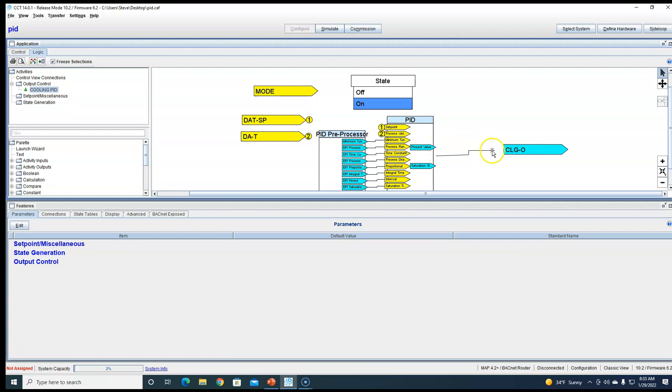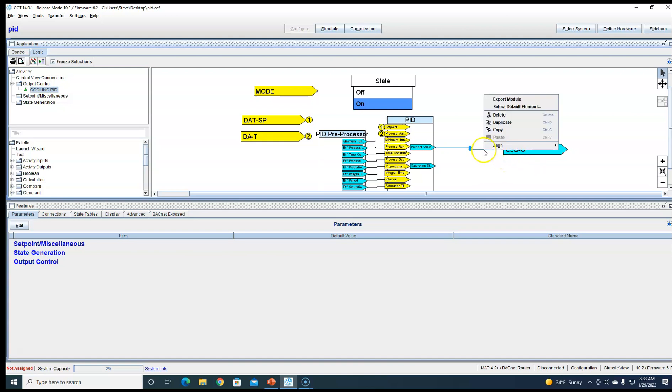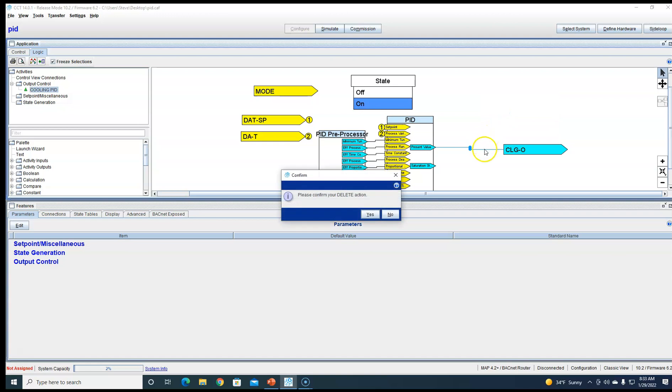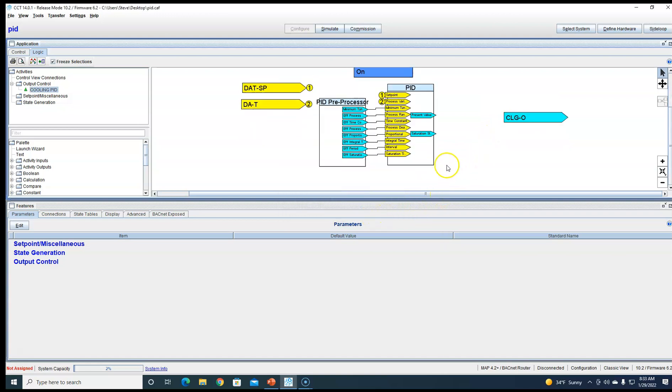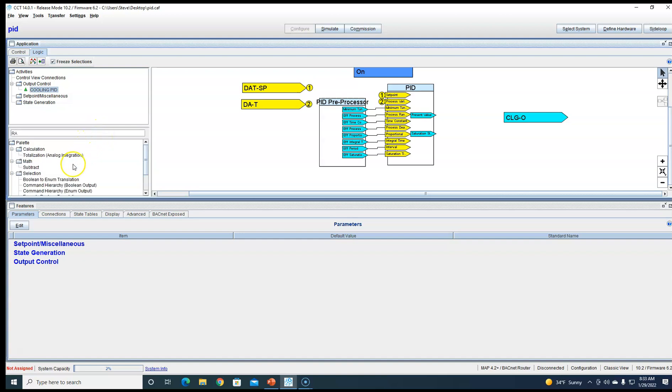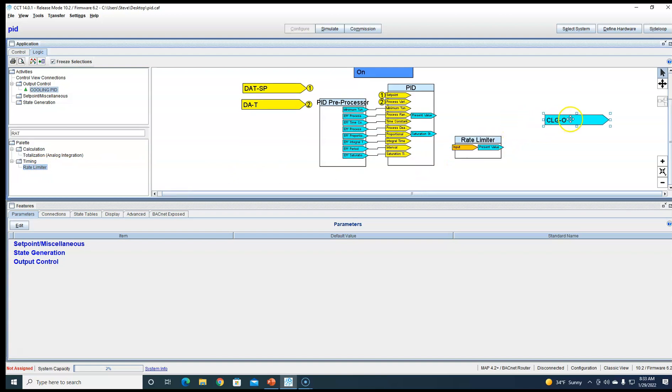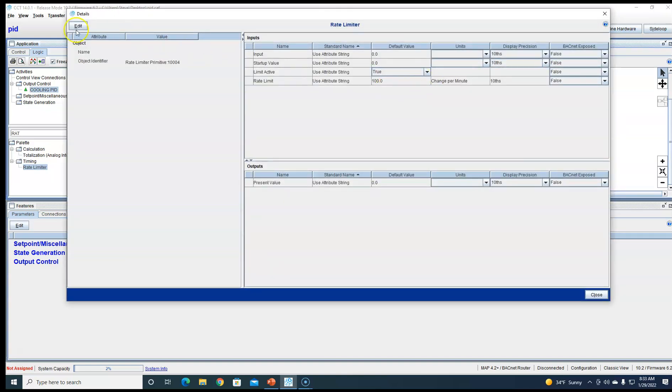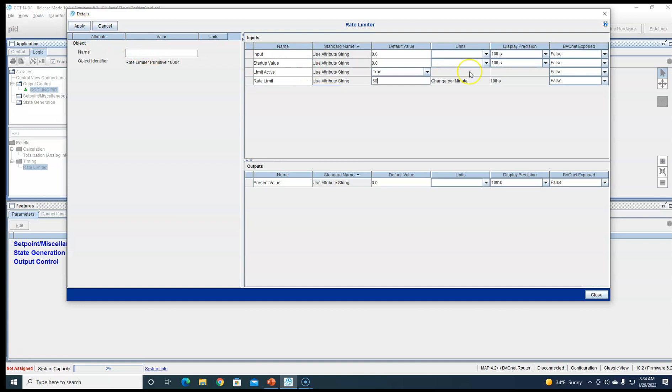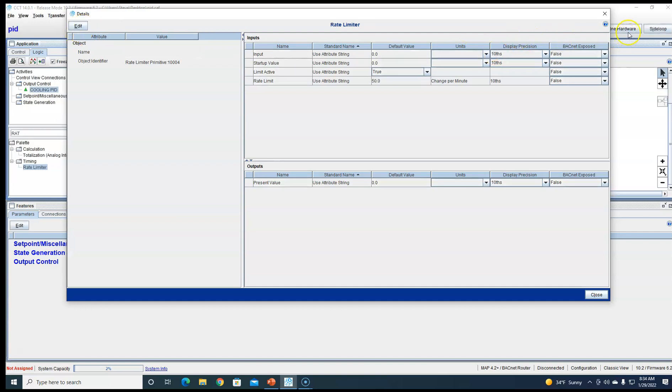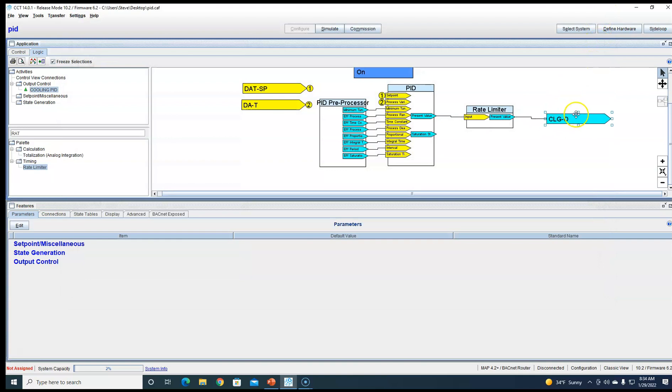Set point to set point, discharge air to discharge air. If you don't like the way that looks, you could always hide these and put numbers in its place. Normally we just connect PID to the output, but today we're going to use a rate limiter. Here to set up the rate limiter, this is changes per minute. So a hundred, that's going to be one minute of change. So if we do 50, that's going to be two minutes of change, so it's going to take two minutes to make a full change.